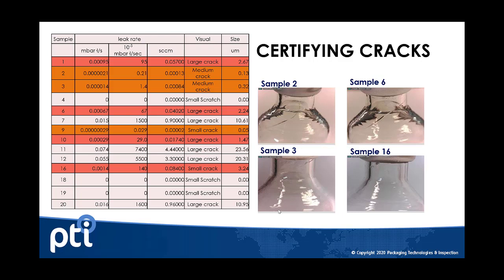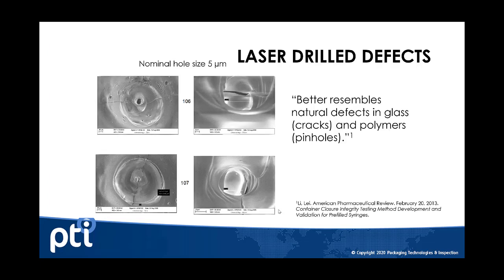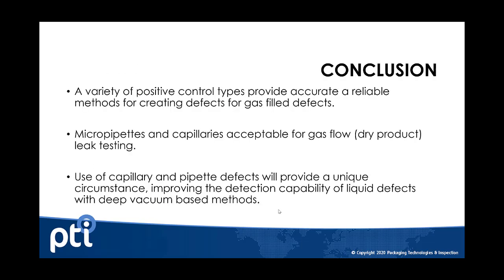In summary, there are a variety of ways that we can produce defects. You can simulate them with a gas-space container using a capillary or a pipette. As you move into a liquid-fill container, simulating that defect with a more real-world defect is critical to properly validate a test method. Micropipettes and capillaries are only appropriate for dry applications, and for liquid-fill containers, the use of laser drilled defects or other real-world defect types are critical to validate that test method.